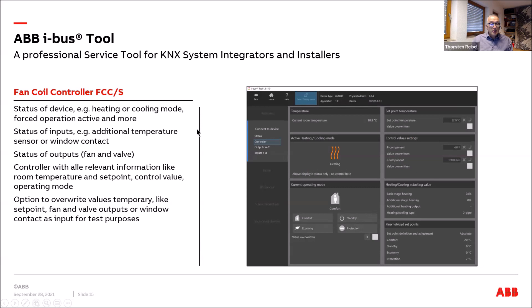The fancoil controller, from the HVAC device range, is a one-channel actuator with four pages. You can view all controller information: heating or cooling mode, actual setpoint or room temperature, and which mode is active. In configuration mode you can overwrite values — change the mode, change a temporary setpoint, or adjust control parameters. Once you disconnect the tool, all original values recover, so changes are only for test purposes.